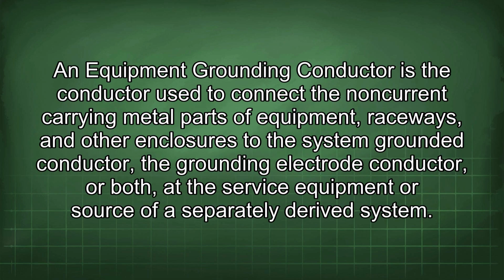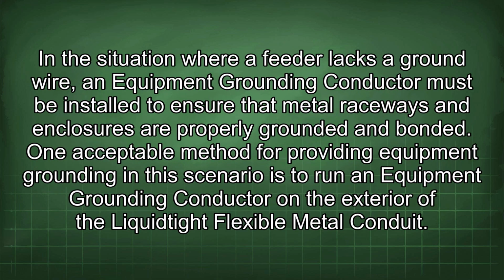An equipment grounding conductor is the conductor used to connect the non-current carrying metal parts of equipment, raceways, and other enclosures to the system grounded conductor, the grounding electrode conductor, or both, at the service equipment or source of a separately derived system. In the situation where a feeder lacks a ground wire, an equipment grounding conductor must be installed to ensure that metal raceways and enclosures are properly grounded and bonded.